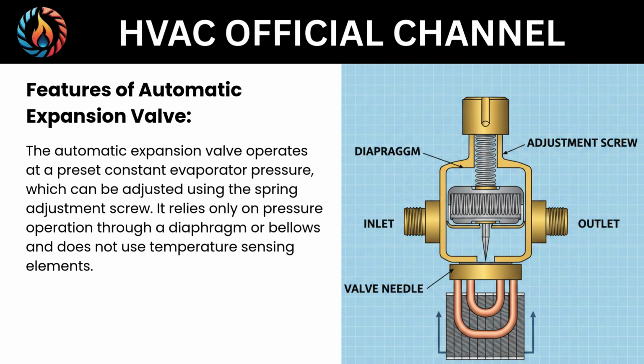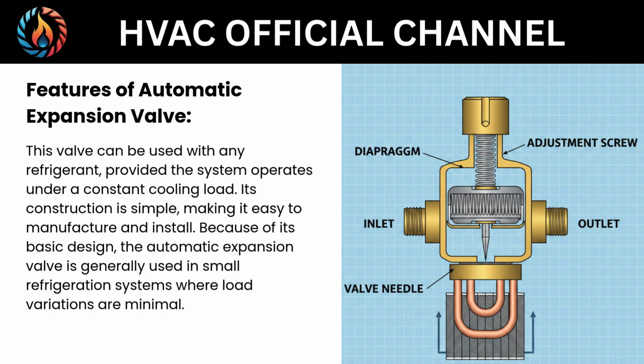Features of automatic expansion valve. The automatic expansion valve operates at a preset constant evaporator pressure, which can be adjusted using the spring adjustment screw. It relies only on pressure operation through a diaphragm or bellows and does not use temperature sensing elements. This valve can be used with any refrigerant, provided the system operates under a constant cooling load. Its construction is simple, making it easy to manufacture and install. Because of its basic design, the automatic expansion valve is generally used in small refrigeration systems where load variations are minimal.